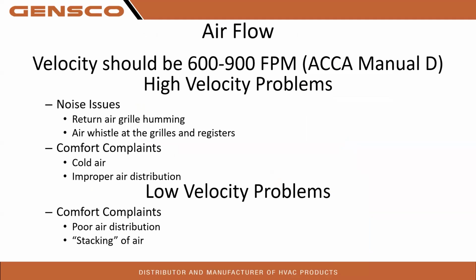Velocity should be 600 to 900, and that's out of the ACCA manual. With high velocity, we could have noise issues, like return air grill humming. You could get harmonics in that return air grill, so we can try to open those up as much as possible to get some airflow over it. Air whistle at the grills and registers. Comfort complaints, cold air. We could be picking up cold drafts from the window. So that's high velocity issues and improper air distribution.